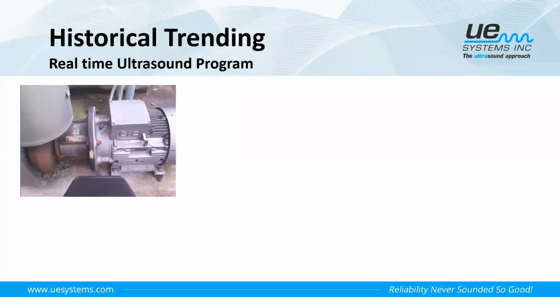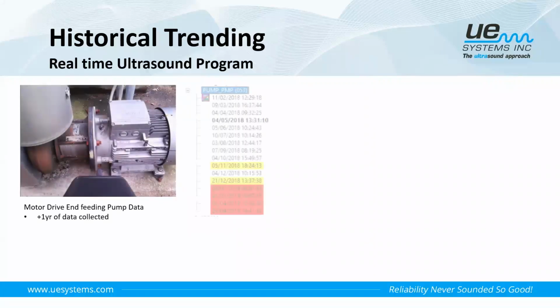So the next one is a motor drive end feeding a pump. With this, we have another year's worth of data, and as we can see now, we're starting to see a few more colors on the chart, indicating that we may be seeing a problem soon.